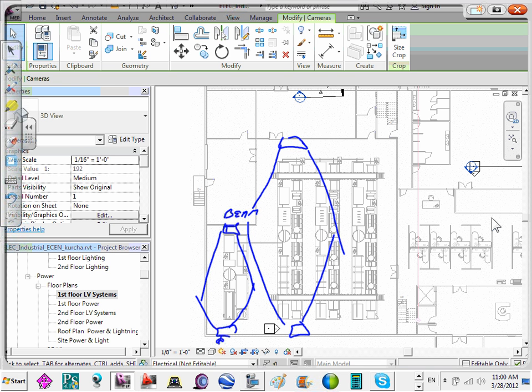So Matt, inside the pipe, do they have a compressor or a fan that pulls the air, or just natural? Yeah, in a VESDA system, it's the main controller. So it has a fan that's constantly circulating the air through these pipes. It's constantly sampling the air. Okay, so there's an air movement.